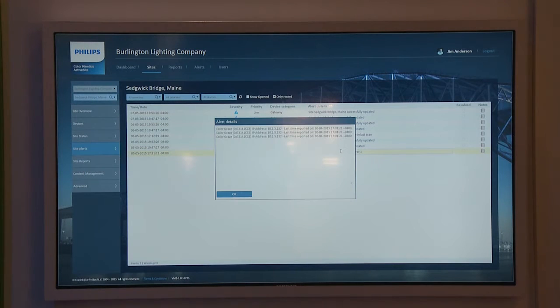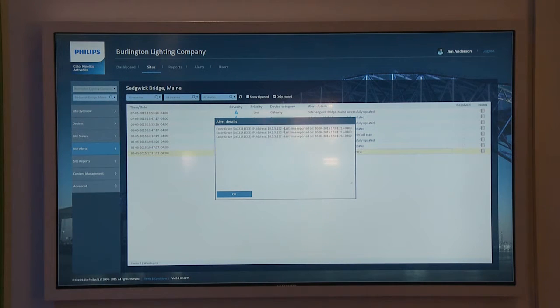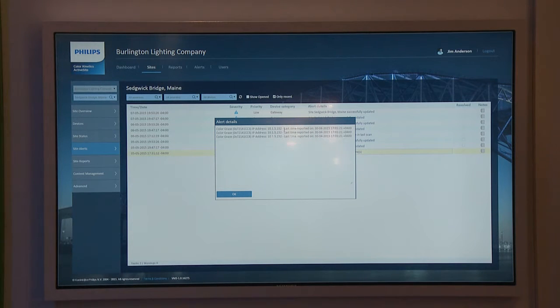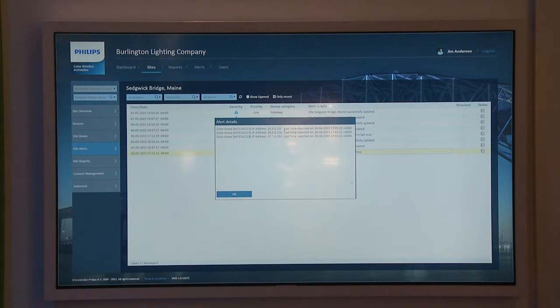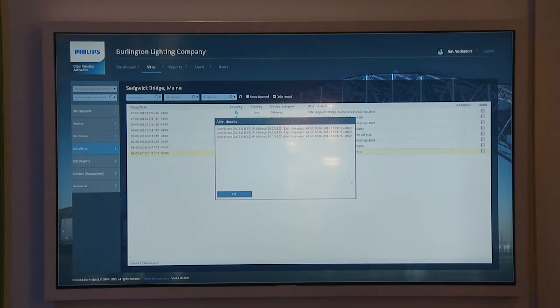The alert says three fixtures failed, with the serial number, IP addresses, and all that information. Where this helps you is that you're able to address a lot of these problems remotely — you don't even have to go to site to replace a fixture. You know exactly which fixture has failed, you can pre-program a replacement, send it to the site, and the installer plugs it back in and it all works fine. That's the kind of information you get.